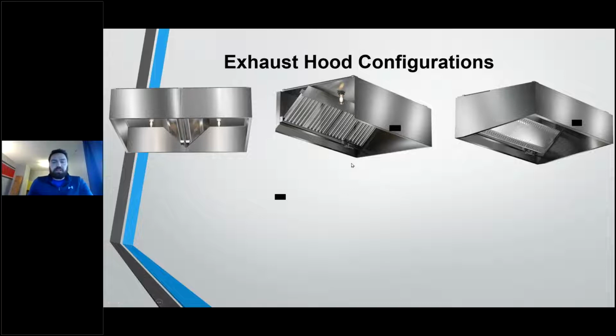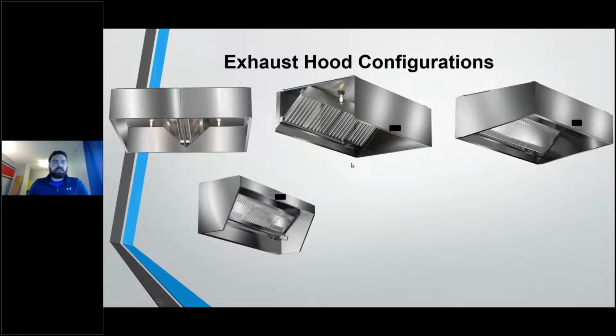So I mentioned 6 inches for those hoods. The other hood in the market is what's called a low proximity hood. Every manufacturer is going to refer to them a little bit differently. You'll commonly hear these in the industry called Five Guys hoods, because the Five Guys restaurant chain was the one that really brought them into existence. But these low proximity hoods are really good for fast food type establishments that are going to be utilizing fryer banks and griddles, but not very hot pieces of equipment.